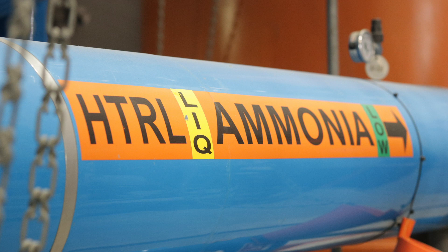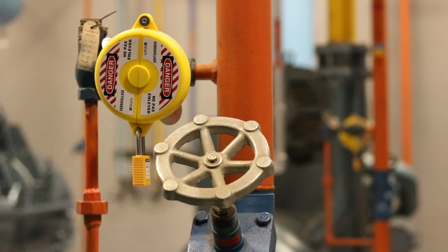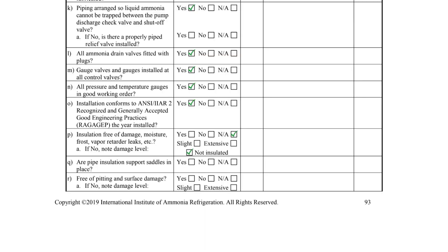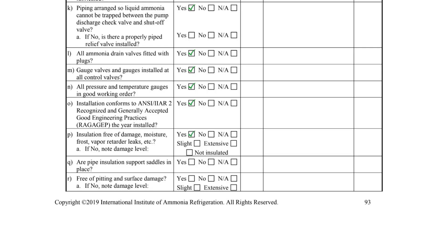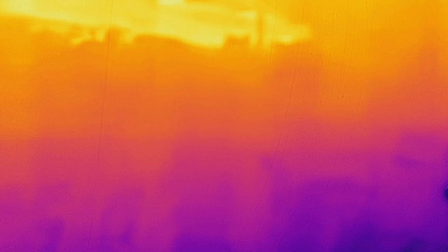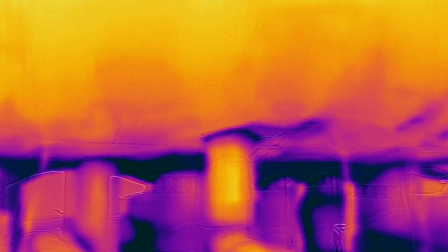When a pipe is insulated, the insulation system must be inspected per Item P. Deficiencies such as jacket damage, breached vapor barrier, and ice buildup must be noted. This pipe is not insulated, so NA and 'not insulated' should be checked. This pipe insulation appears sound, so YES can be checked. A thermal imaging camera can be helpful to identify insulation system failures that cannot be observed with the naked eye.